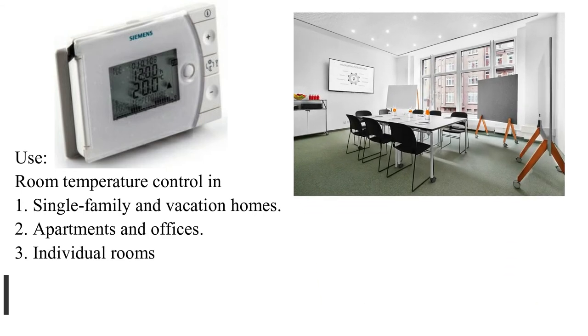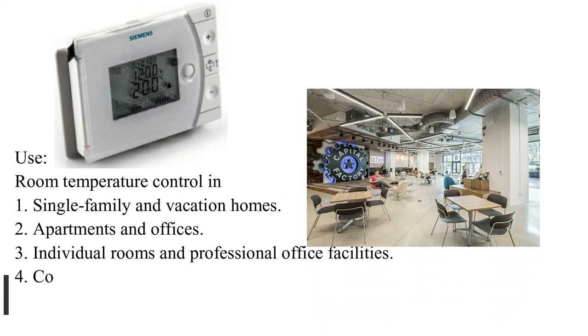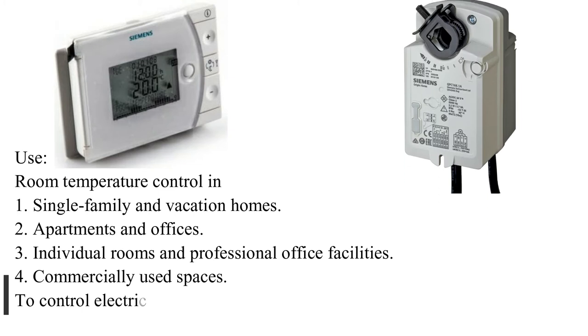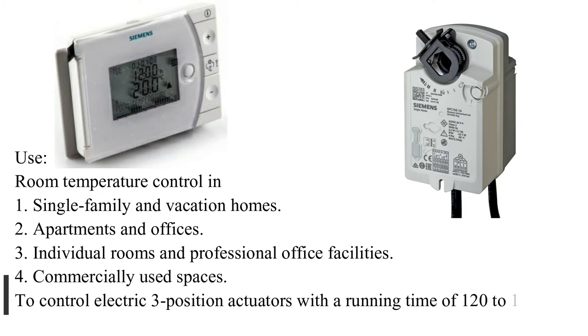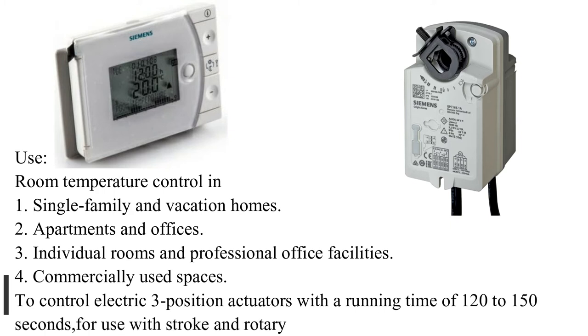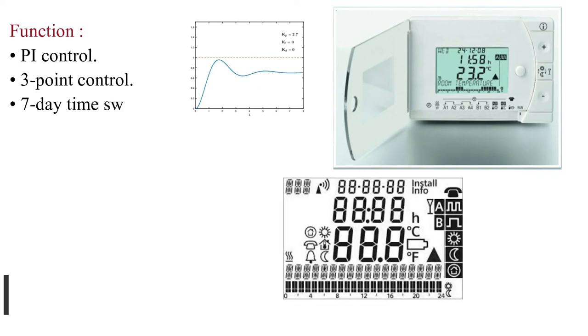7) Heating zone control. Use: room temperature control in single-family and vacation homes, apartments and offices, individual rooms, and professional office facilities for commercially used spaces — to control electric 3-position actuators with running time of 120 to 150 seconds for use with stroke and rotary actuators.